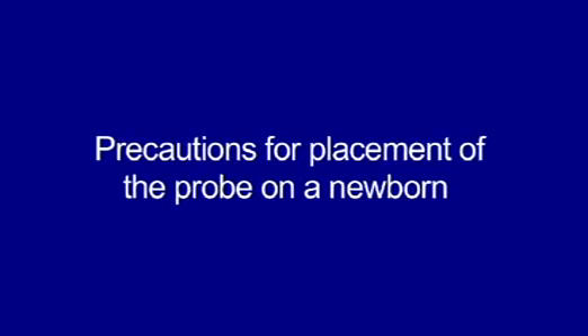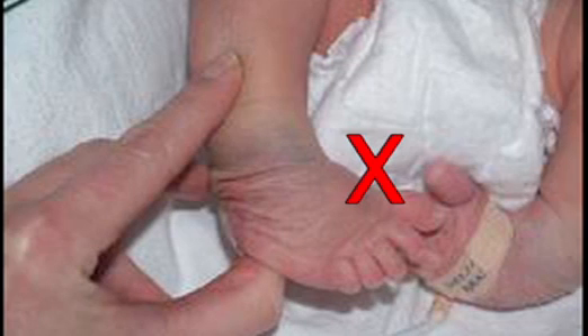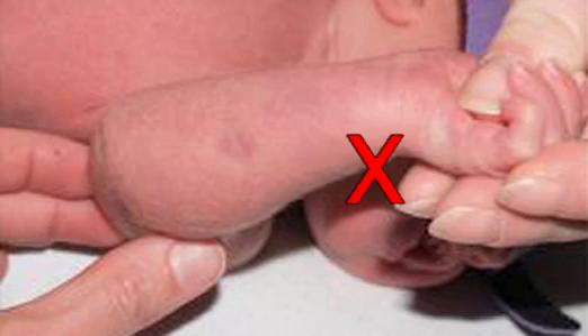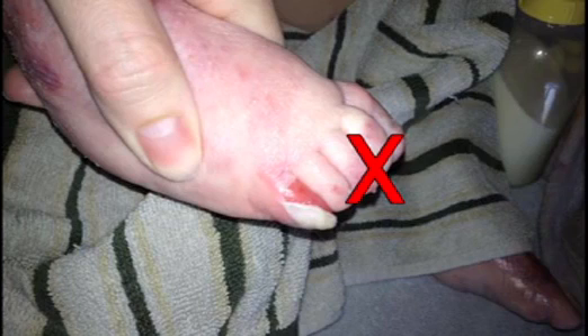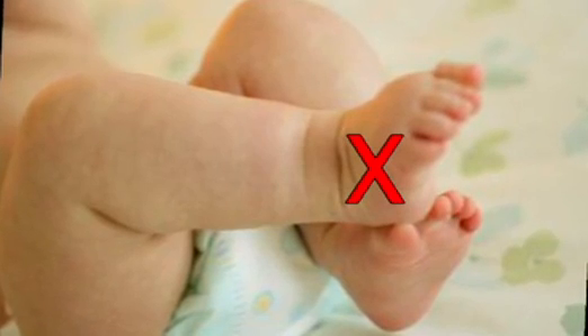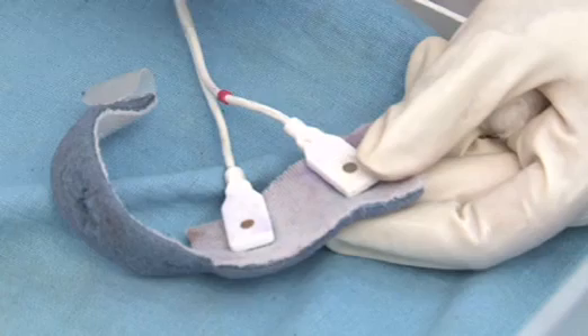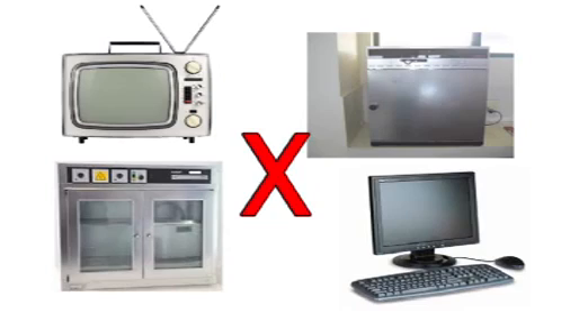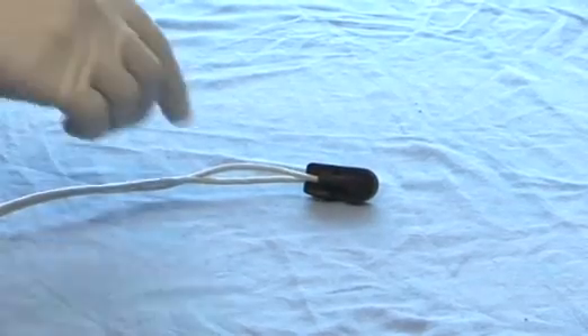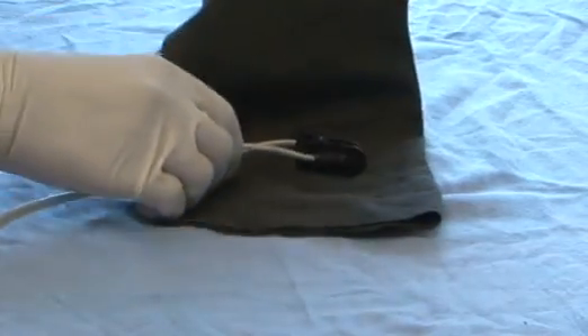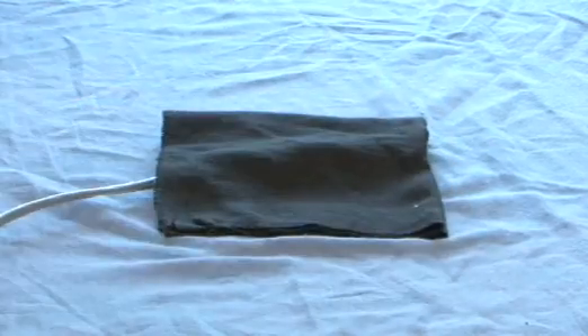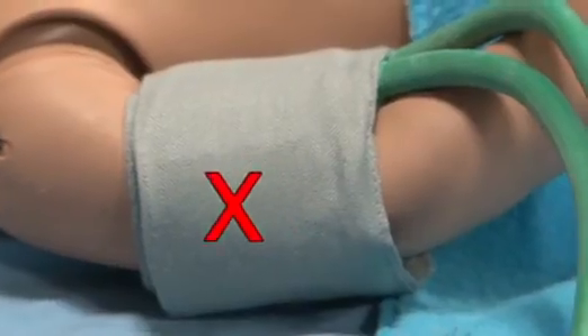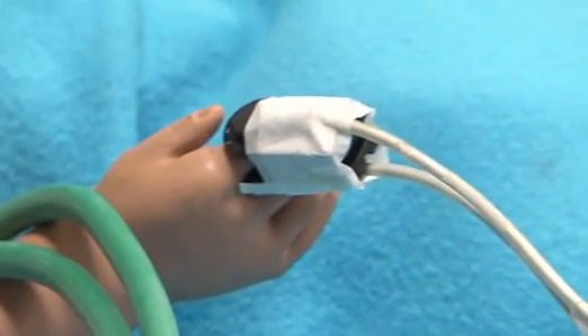Precautions for placement of the probe on a newborn. Avoid edematous, bruised sites and excessive pressure. Look for skin reddening, blistering and discoloration, etc. because of the sensor placement. Keep probes away from direct light or electromagnetic equipment. Do not allow excess ambient light to shine on the probe. If that happens, cover the probe with an opaque material. Do not tie the BP cuff proximal to the limb where the probe is fixed.